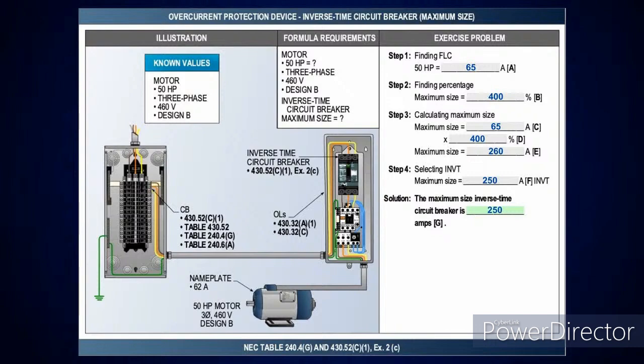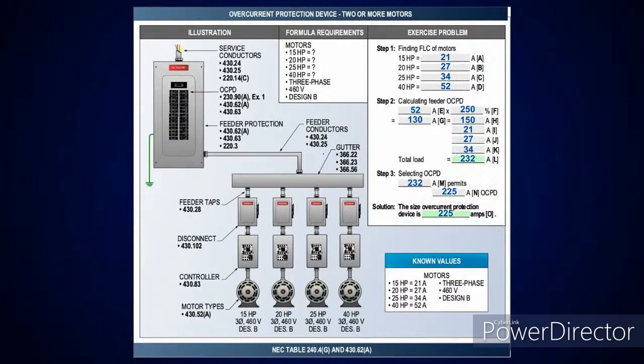Now, the next one I'm going to get into is where I have multiple motors. When you get into the multiple motors, like we talked about, we used to actually have this in our publication a little bit different. We used to take and do the calculation and drop down to the next standard size, add them up, and then go up to the next standard size. Well, the code making panel came in and they said, no, we want to do it this way. We want to take and calculate it, go up to the next standard size, add them up, and then drop down. Okay? So we changed this up from what they did, and that's probably like 3 cycles ago.